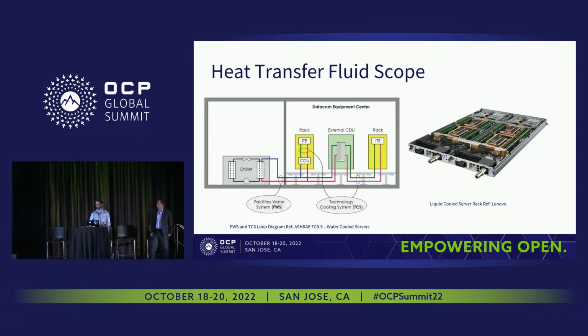Within a data center facility, there will typically be two fluid circulating loops directly involved in cooling IT equipment with a CDU barrier in between them. On the facility water side, there will be a heat transfer fluid that carries heat from one side of the CDU and rejects it in some type of cooling system, such as a chiller.